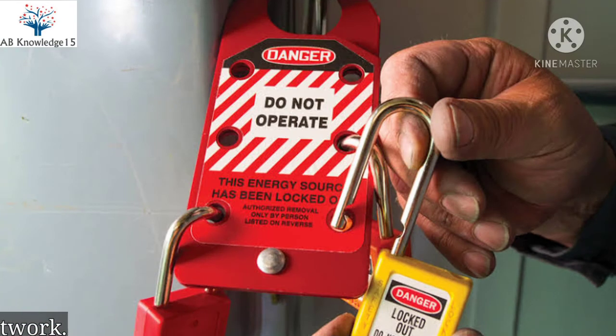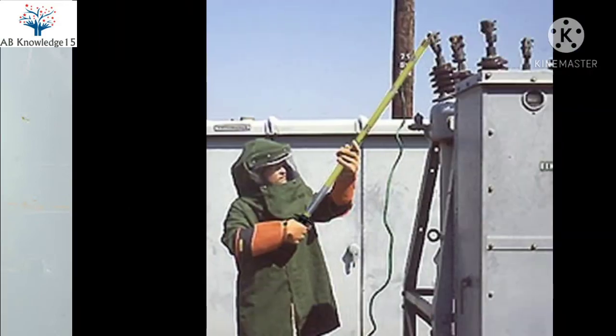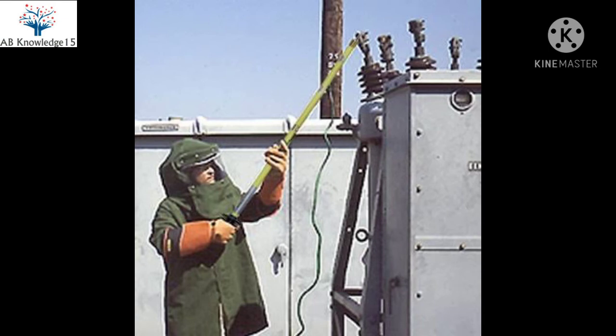Shut down the transformer and apply lockout tagout from both sides of the transformer so that it does not mistakenly get charged or switched on during the testing. Discharge the transformer's winding so that there is no charge left in the winding, and for safety purposes discharge the transformer from both the primary side and secondary side.